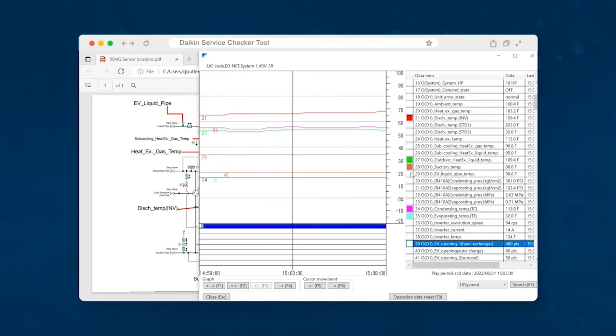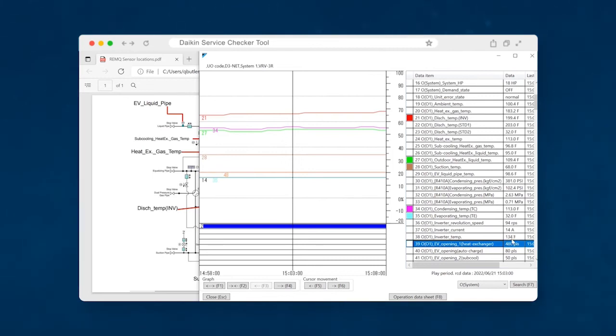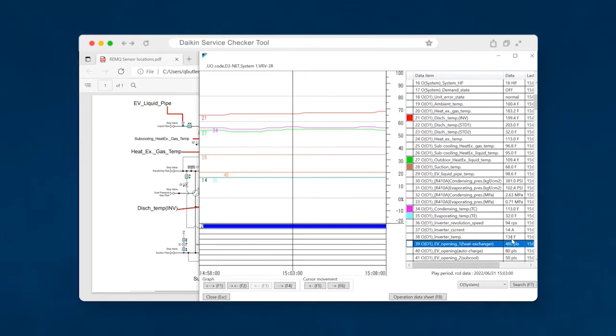Look at your outdoor heat exchanger position. Notice this one is at 480 and the four-way valve positions have the outdoor heat exchanger in a position to be a condenser. But oftentimes in those shoulder seasons or in the winter time, your outdoor unit is acting as an evaporator. So the heat exchanger in the outdoor will be an evaporator and it might want to pinch this valve off to zero pulses, because it's going to basically control like an indoor unit. It's going to have superheat control across that heat exchanger. And so, if that valve closes all the way off and you've still got refrigerant flowing through it, that refrigerant's uncontrolled, and so, you're going to be flooding the compressor out.